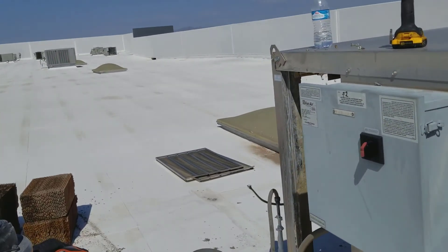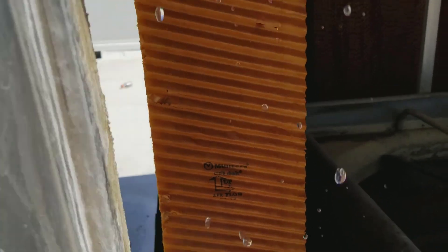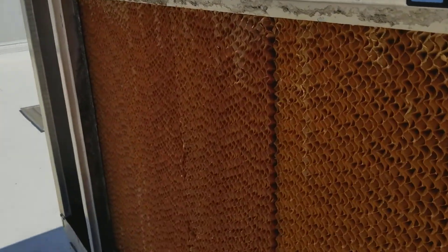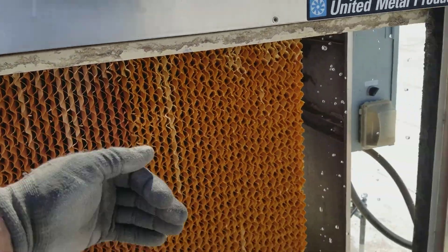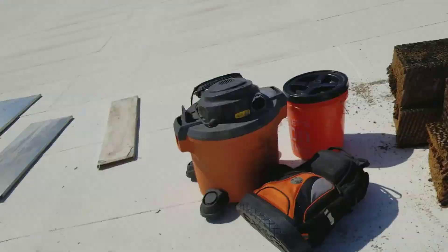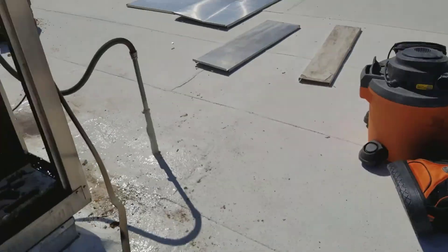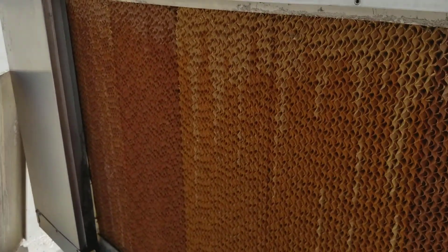Now one thing on these — you have to watch the arrows. It says 'up' and that way for airflow. You want the 22-degree angle in, and then the acute 45-degree angle — which you can't see now because I put the CELdek in — but it's a sharp angle right here. That goes towards the outside because that carries the water to the outside. If you put these in backwards, the water will run inside towards the fan and the airflow will just pull the water right down into the space.